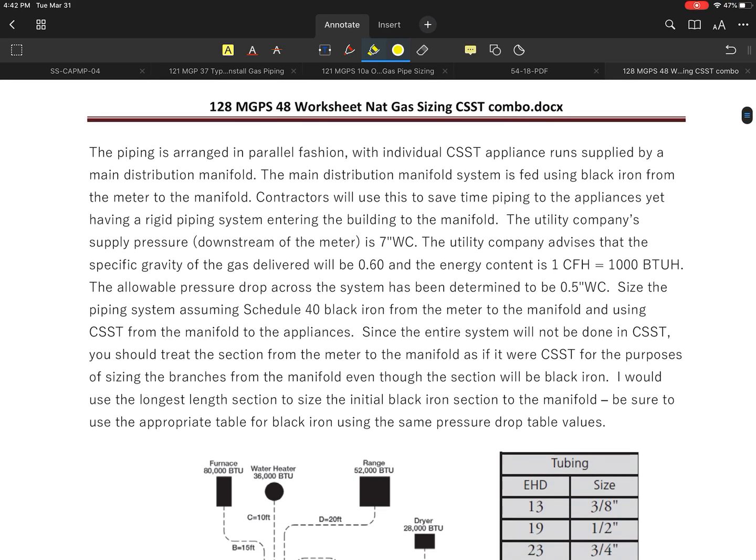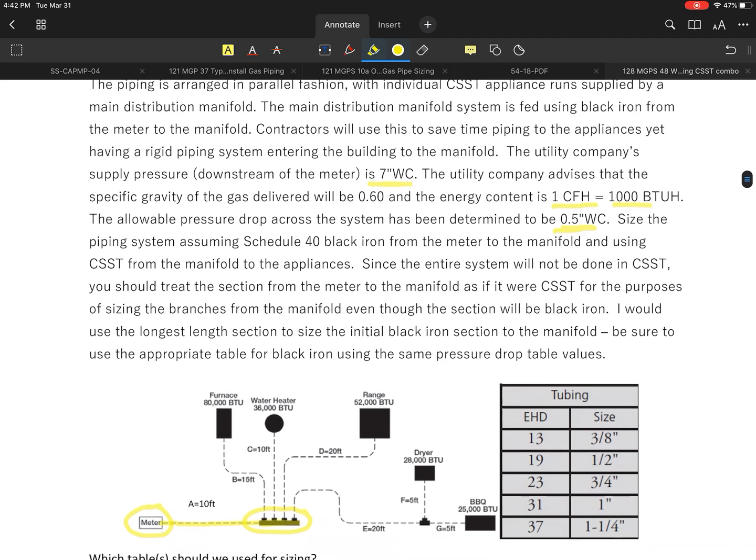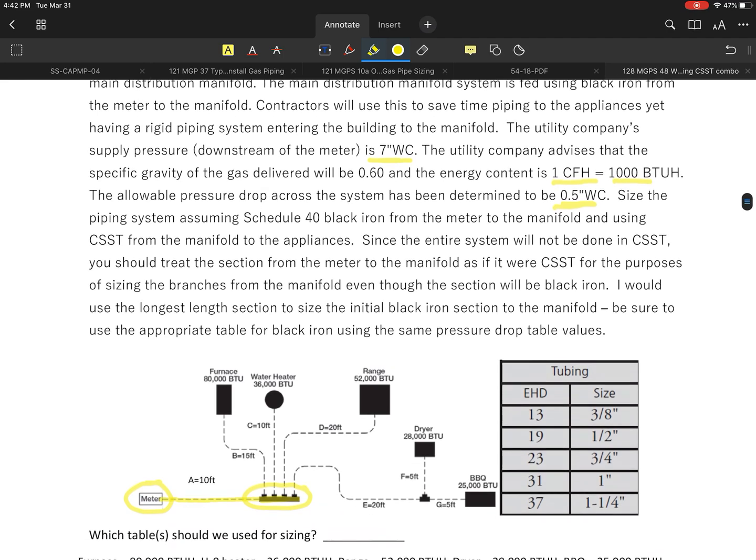I'm going to do this as a very typical system where I'll feed the building at 7 inches, and I'm going to use a typical pressure drop of 0.5 inch water column. I'll use a very basic 1000 BTU per cubic foot.